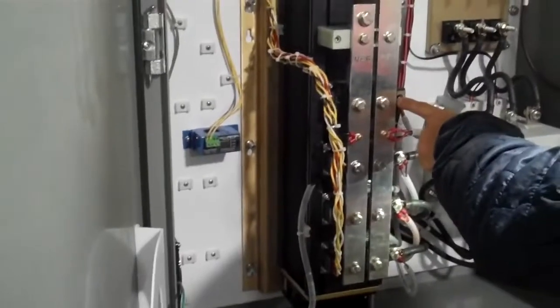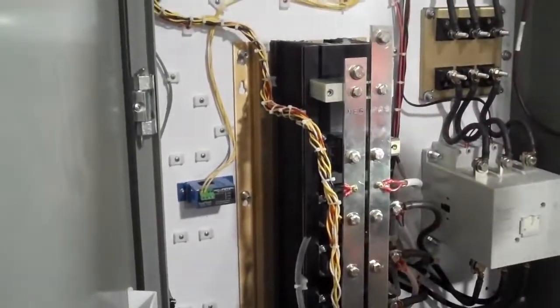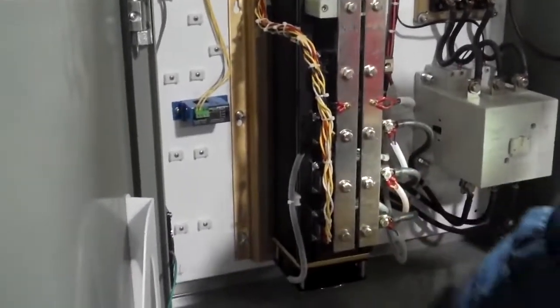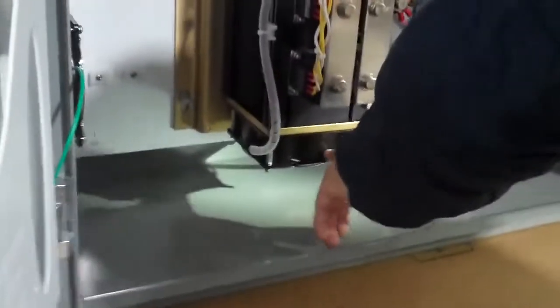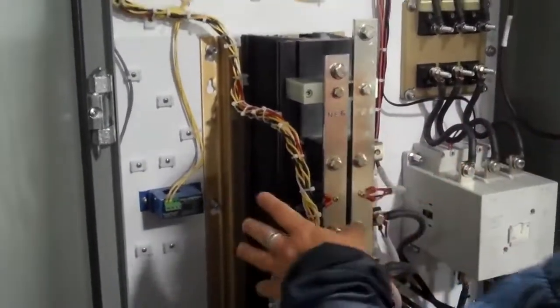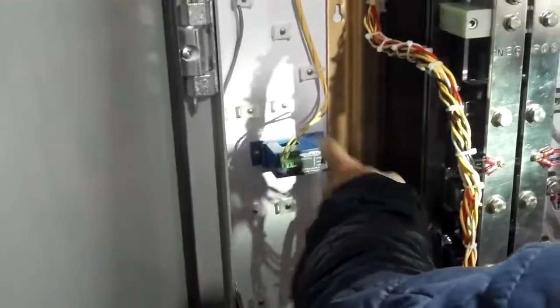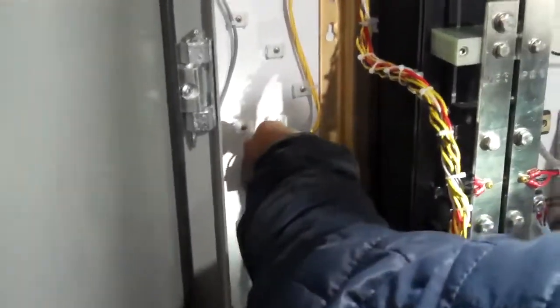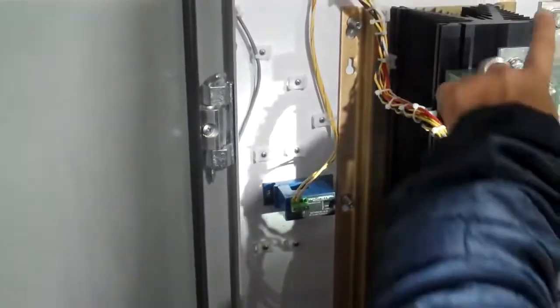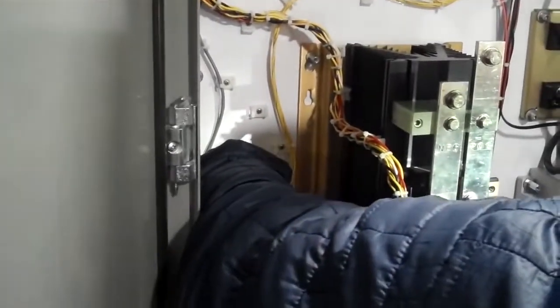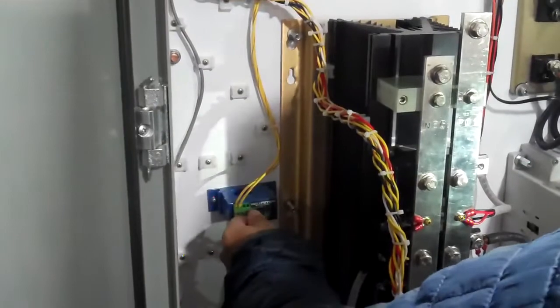And here we have our DC bridge with its freewheeling diode. We have the positive and the negative output of the 3 dual SCRs. And here we have the bridge 120 volt fan. Notice that there is no electronics attached to this assembly. On the left hand side we have the current transducer, and this cable is just getting the control power. Then what we don't have is a connection between the negative bus bar going into this current transducer to pick up the 4-20 milliamps.